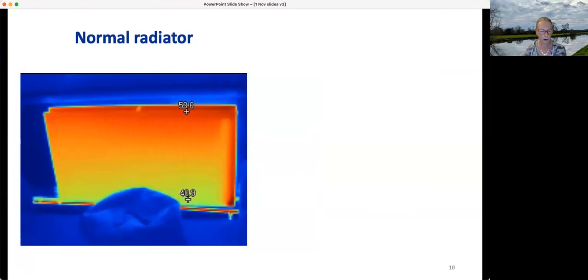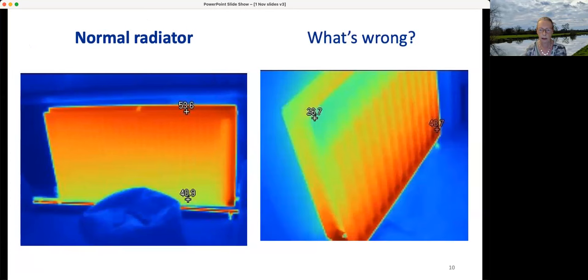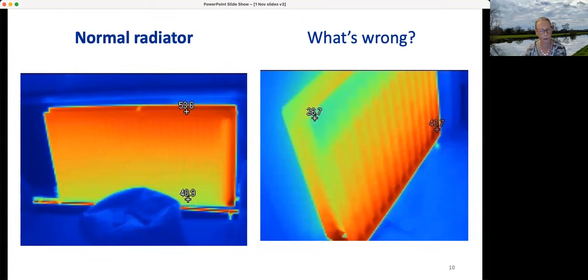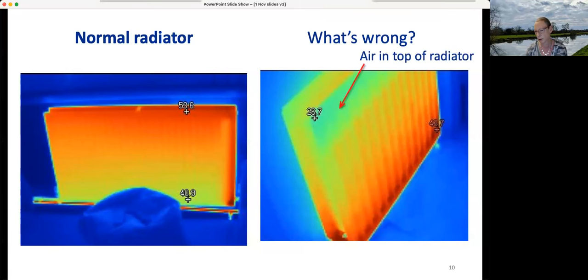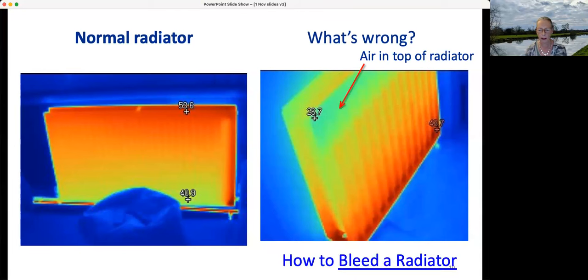Although we're talking primarily about heat loss, it's also interesting to look at heating systems. Here's a normal radiator functioning correctly, and this other radiator isn't — it's not nearly as hot. The reason is pretty obvious: it's got air in the top. You can bleed it. There are other things that can go wrong with radiators, but this is a very common one and very easy to fix.